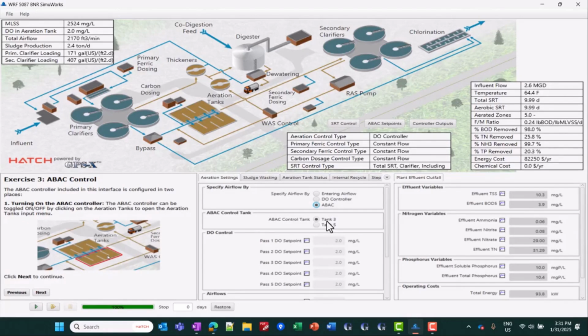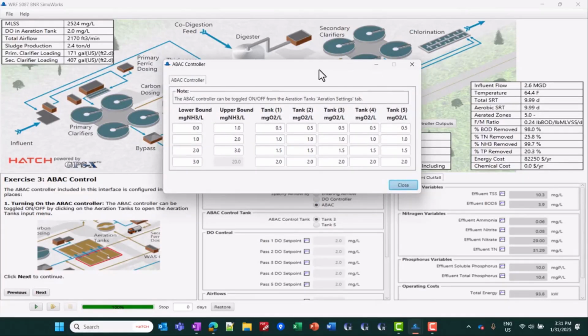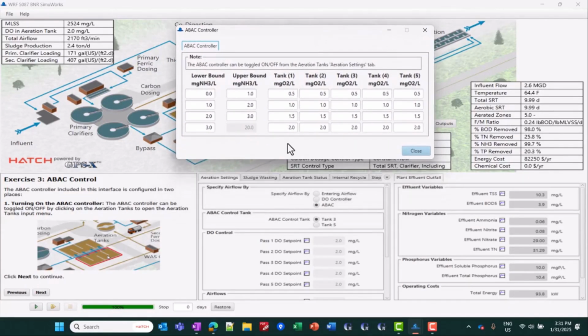So we're going to leave it here at tank number 3, and we're going to look at these ABAC set points. What this does is we take that ammonia signal and look up in this table what we want the DO set point to be. So for example, if it was half a milligram per liter of ammonia, then we'd be in the first row here and we would be using these relatively low concentrations of DO, half a milligram per liter across the board. But if the ammonia started to rise, say we're having an increase in loading to the plant and the ammonia went up to a higher value, 2 or 3 milligrams per liter, then we would move up this table and we would start increasing the DO set point.